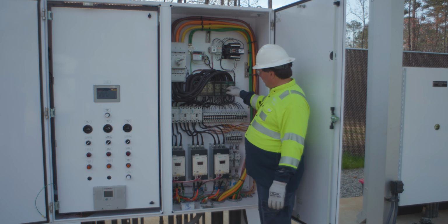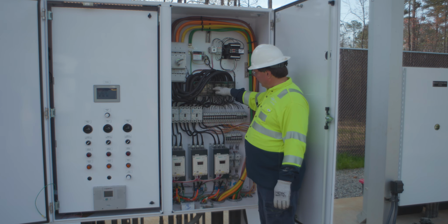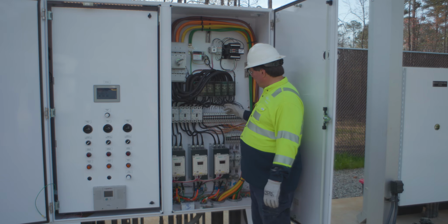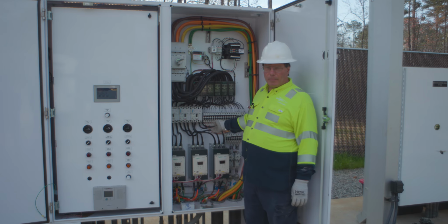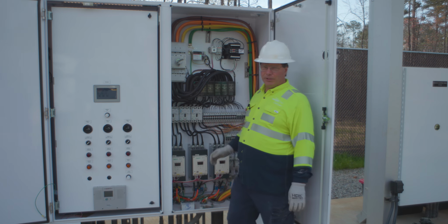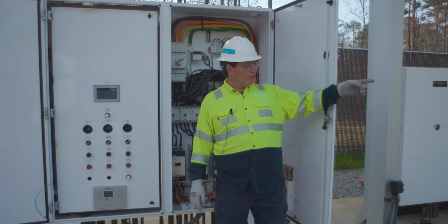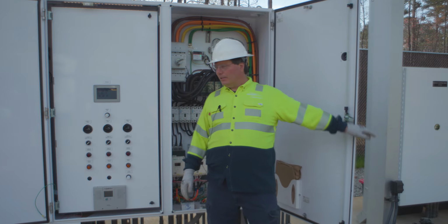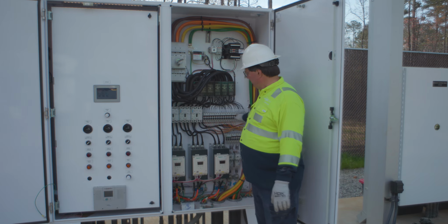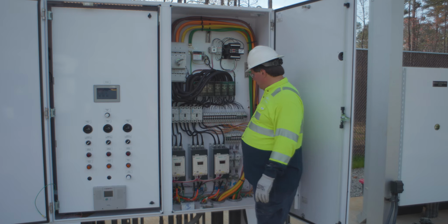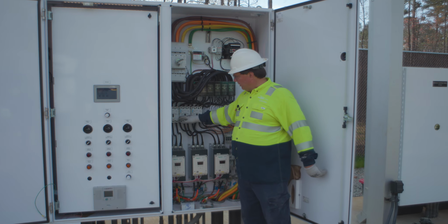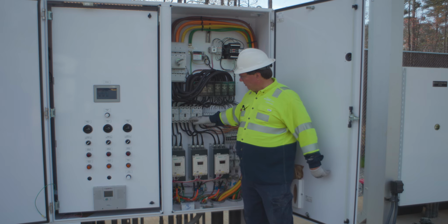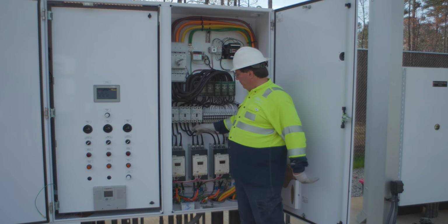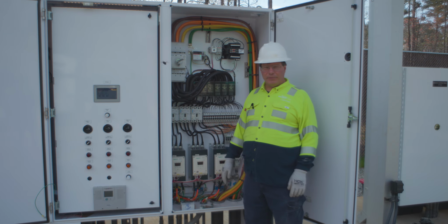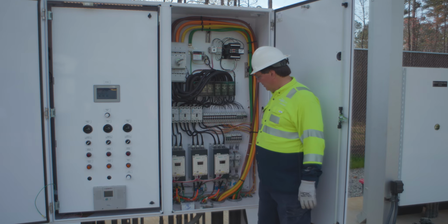Then it gets distributed in these terminals to various pump breakers, grinder breakers, valve breakers. So all those motorized valves and the grinders are all run from these breakers over here. The main breakers, these three breakers are for the pumps 1, 2, and 3. They're 150 amp for 125 amp pumps.